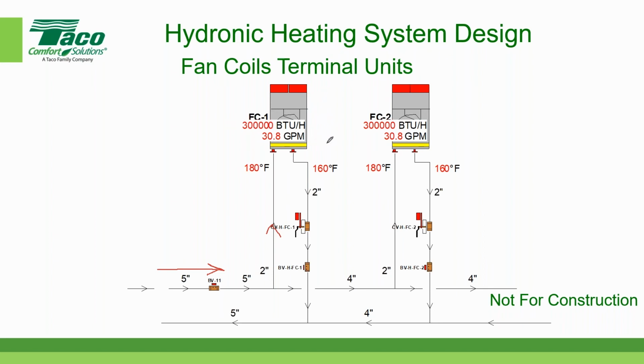300,000 BTUs, roughly 30 gallons per minute. The supply water temperature is 180 degrees. Return water is 160. Here's our control valve. And usually for larger units like this, 300,000 BTUs, that control valve is a modulating control valve. And then we also have a balancing valve over here. And the way we typically balance these systems is we open the control valve 100%. We set the pump at the design speed that we need.